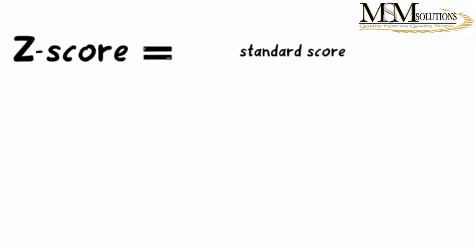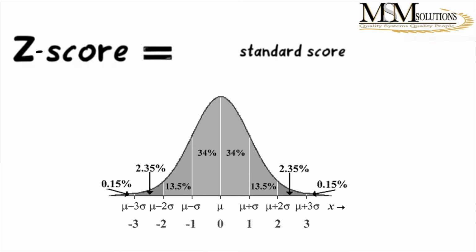A Z-score can be placed on a normal distribution curve, and you will then look at Z-score ranges from +3 standard deviation to -3 standard deviation of your normal curve. And you would then say that if your results are outside those plus and -3 standard deviation, the results are unacceptable. Other times you would even reduce that. You'll find some PT saying that the acceptable limit is within plus or -2 Z-score, and then anything outside that would need to be investigated.